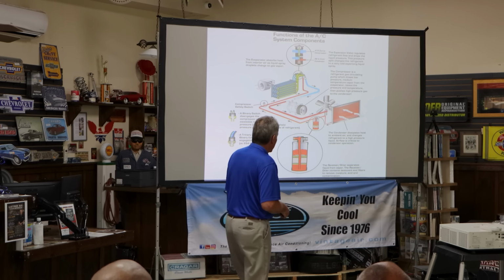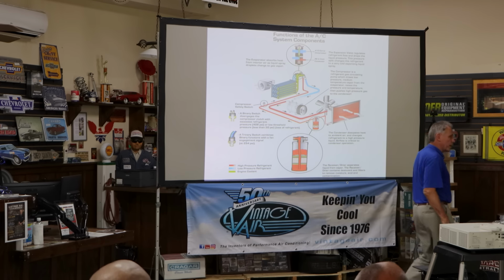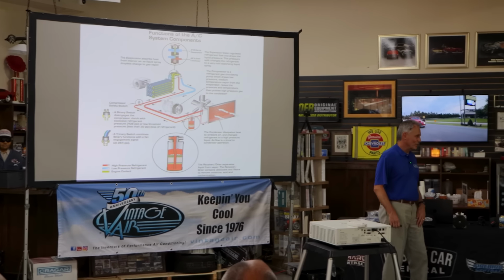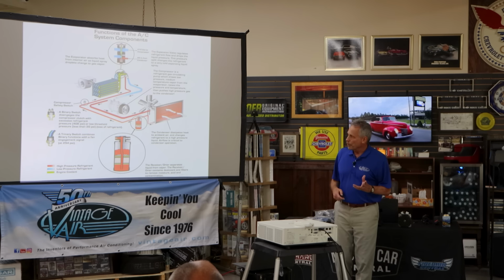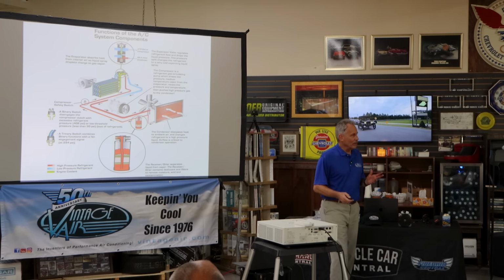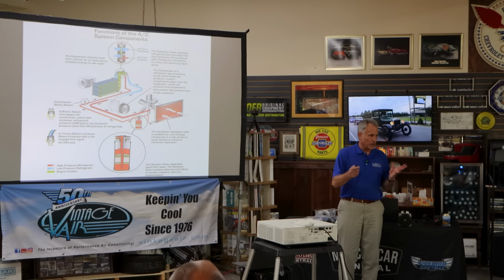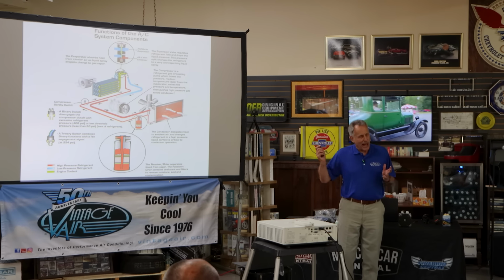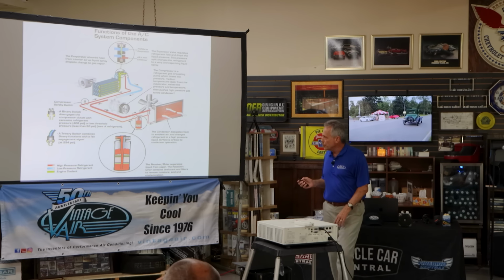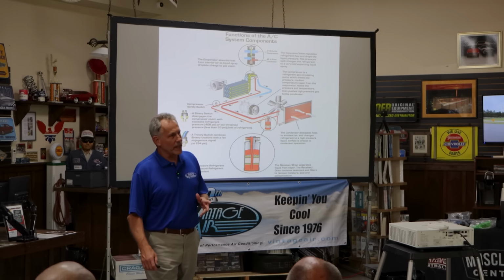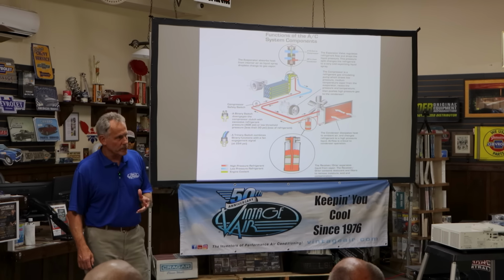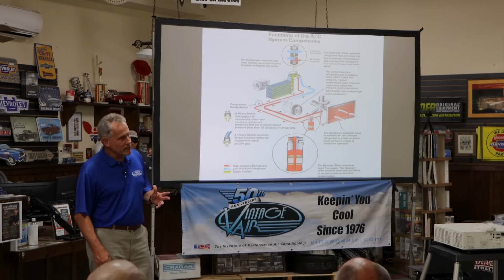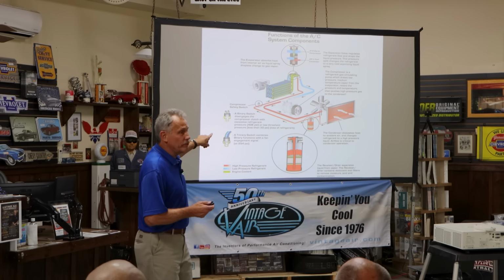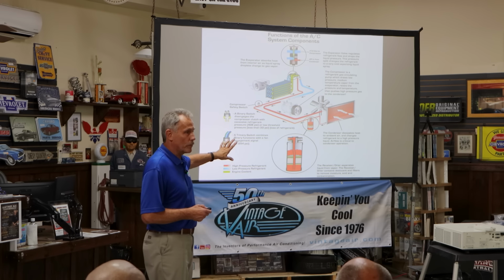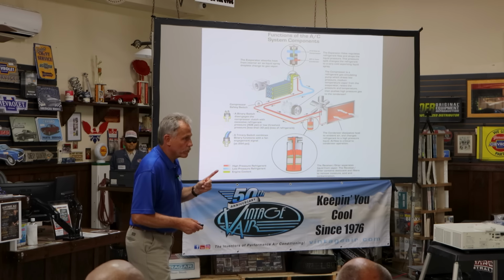So, guys, you did R-12 systems years ago. You remember we just had a low pressure switch? Low pressure switch used to go in there. When you charge a system, you're going to be around 30 psi before you start the system, just in a latent mode. So you're going to be a little higher than that. But a low pressure switch would prevent the compressor clutch from being engaged if the system pressure was below 30 psi. Below 30 psi, can't turn the compressor on. That saves you from destroying the compressor in the system. Okay? That was a low pressure safety switch.